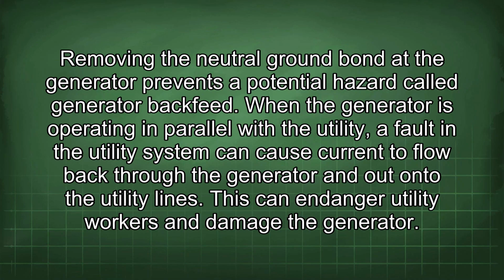Removing the neutral ground bond at the generator prevents a potential hazard called generator backfeed. When the generator is operating in parallel with the utility, a fault in the utility system can cause current to flow back through the generator and out onto the utility lines. This can endanger utility workers and damage the generator.